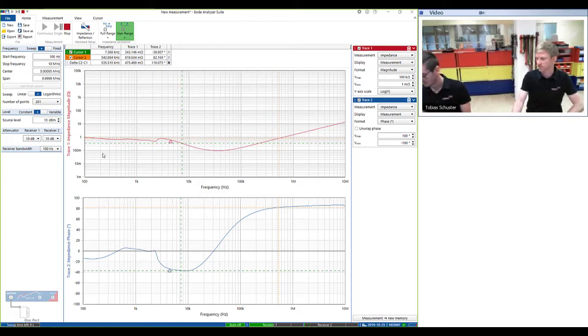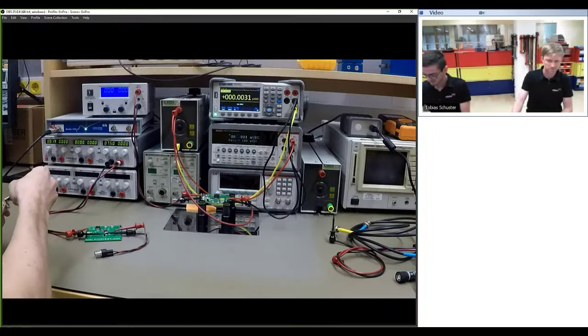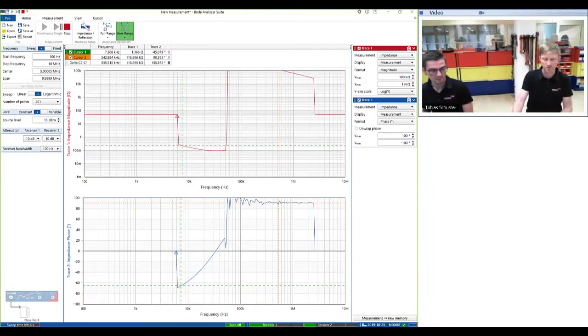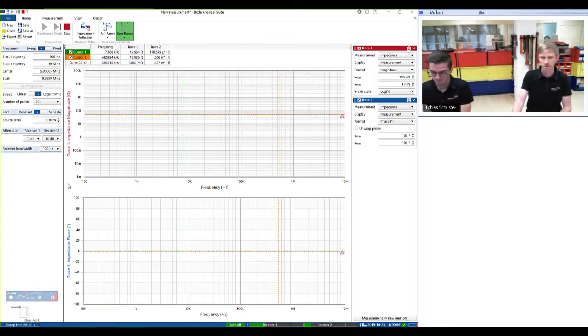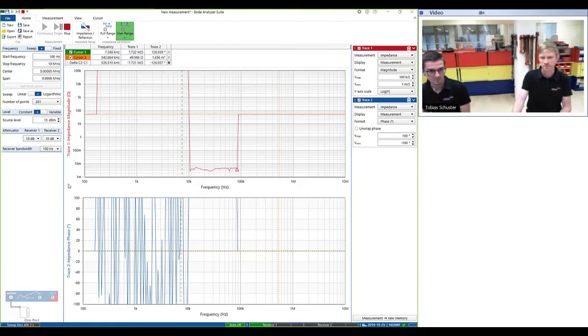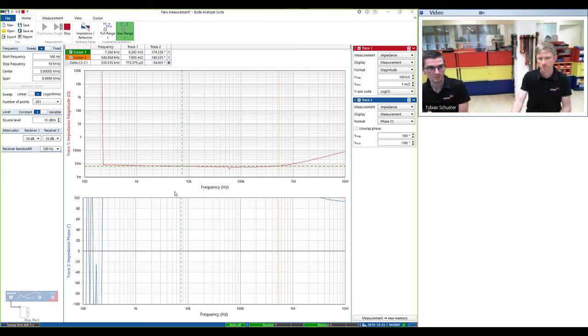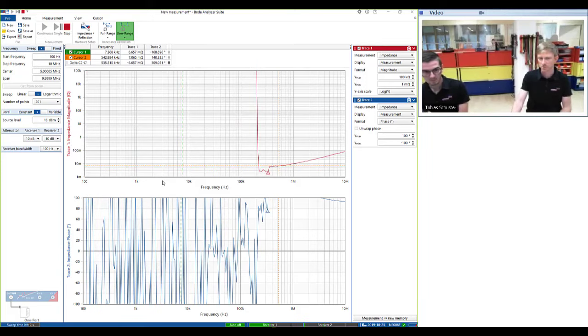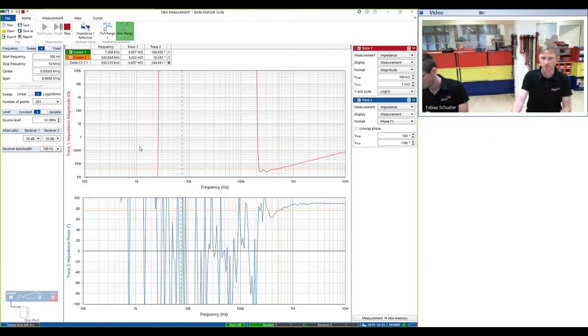Something is wrong, Tobias. Probably might be an error in the calibration. Can we do the calibration again? Check that first. We'll connect the 50 ohm again. So 50 ohm, that's perfect. That's fine, nice and flat. I think we do the short again. Probably the open. Open is beautiful. Short again, please. Yeah, good enough. Below a milliohm.